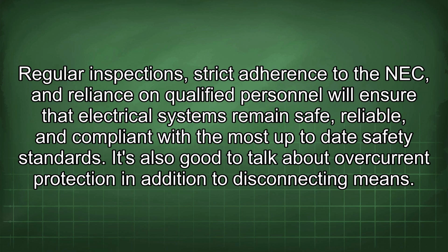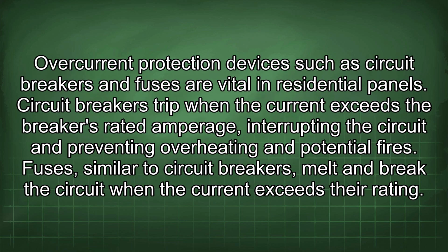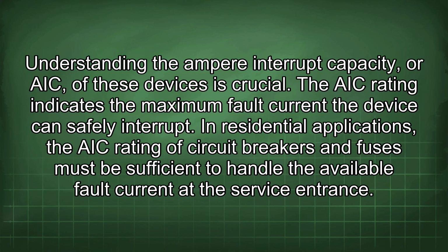It's also good to talk about overcurrent protection in addition to disconnecting means. Overcurrent protection devices such as circuit breakers and fuses are vital in residential panels. Circuit breakers trip when the current exceeds the breaker's rated amperage, interrupting the circuit and preventing overheating and potential fires. Fuses, similar to circuit breakers, melt and break the circuit when the current exceeds their rating. Understanding the ampere interrupt capacity, or AIC, of these devices is crucial. The AIC rating indicates the maximum fault current the device can safely interrupt.